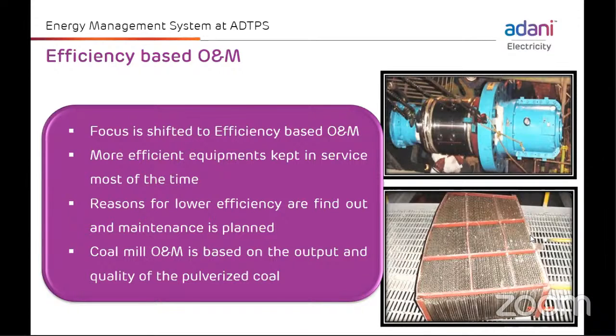We always keep more efficient equipment in service where there is standby equipment. For example, if there are 2 boiler feed pumps, the most efficient equipment we always keep in service and the other as a standby. And we carry out the analysis of the reasons for lower efficiency, and accordingly we plan the maintenance during the opportunity.